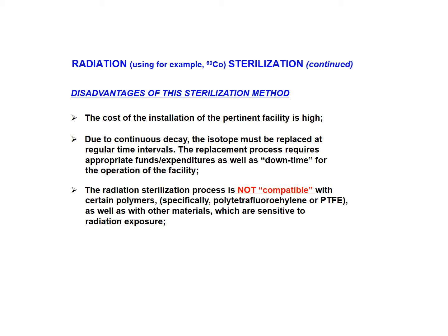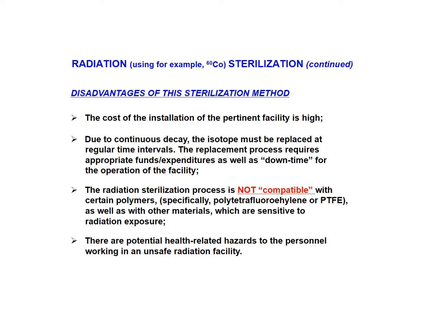One other aspect that must be kept in mind is that radiation sterilization is not compatible with certain polymers. Biomedical engineers must be aware of that and must make sure that those polymers are not exposed to radiation sterilization. What is detrimental is that exposure to radiation breaks down the backbone of polymers and therefore changes not only the chemical composition but also the function of the device which is composed of these polymers. One may be under the impression that a certain polymer is the one out of which the device is composed and therefore will function, and the actual performance inside the human body might be totally different.